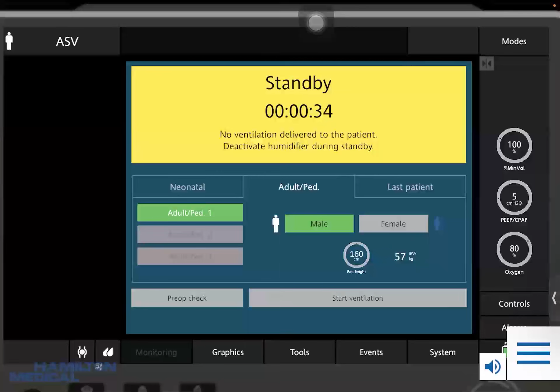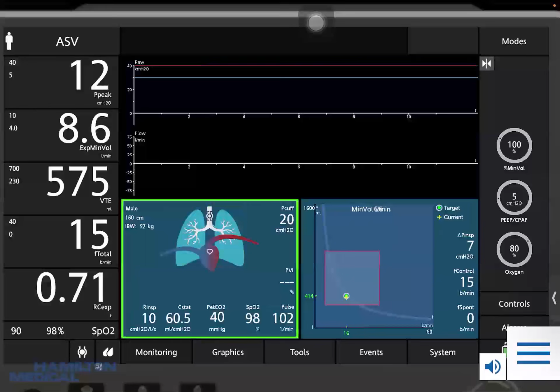Likewise. So what the ventilator does, it would initially give a few control breaths, and it will calculate the thing called plateau pressure and the expiratory time constant, so that they will decide an optimal respiratory rate for that patient. Like here, this is 16, and they will calculate a minute ventilation. So this is a minute ventilation, and these are the possible tidal volumes and respiratory rate that can achieve that targeted minute volume. So if the patient doesn't reach that tidal volume, the ventilator will increase the pressures, or if the patient delivers more tidal volume, it will reduce the inflation pressures to match that target.